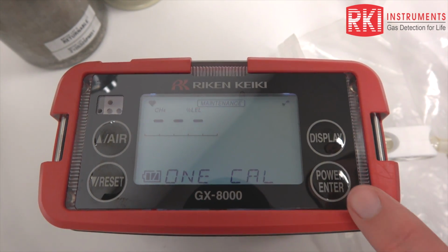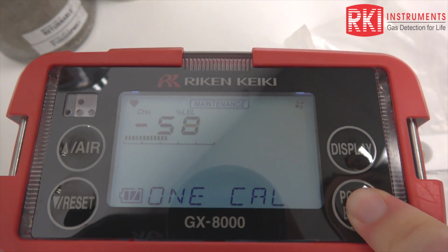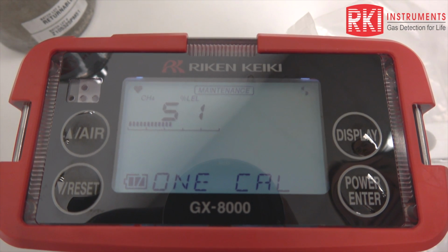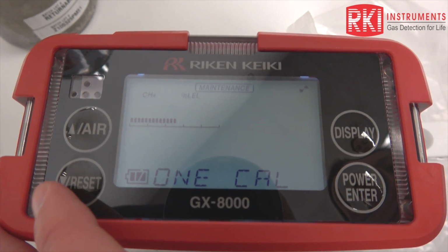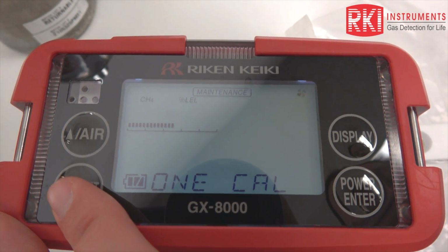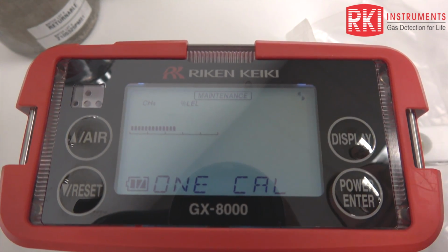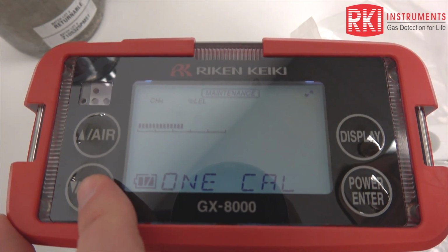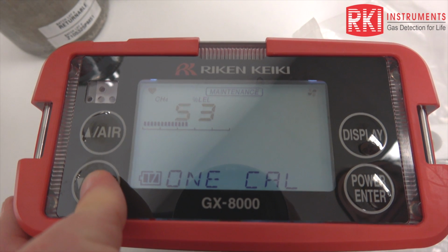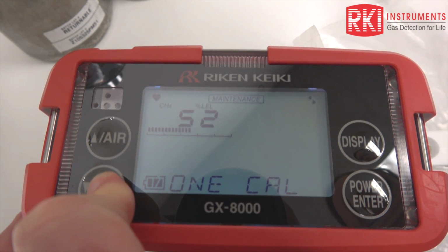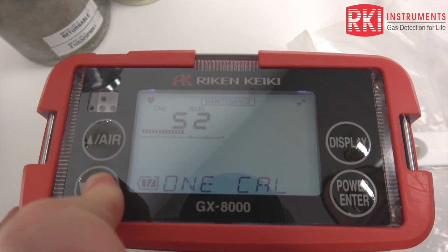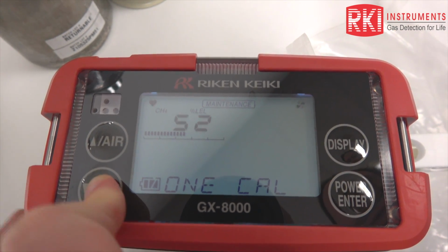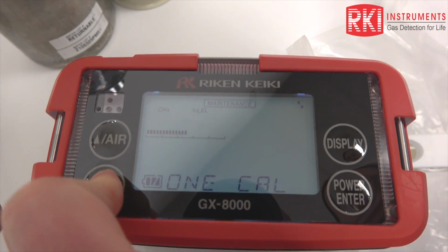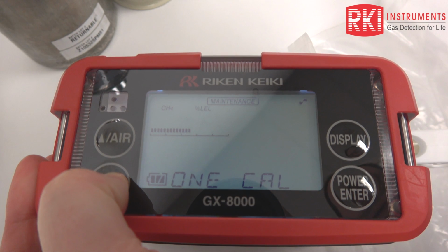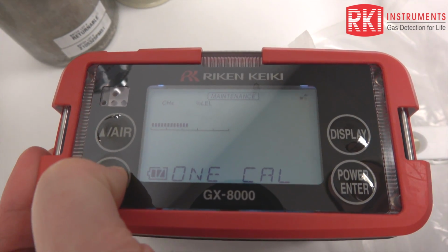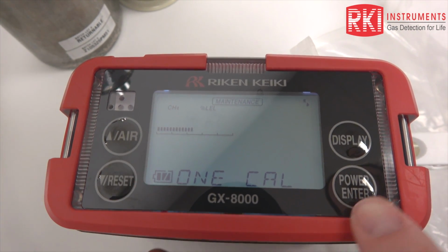We're going to start with the LEL combustible. I am using 50% LEL methane for my calibration. You need to use whatever gas is appropriate for your application. And it's also important that you calibrate the LEL combustible sensor before you calibrate the percent volume combustible sensor. Percent volume levels of gas will hurt your LEL sensor, and you need to let it have enough time to settle back down. So I need to get this reading to go down to 50% LEL because that's the concentration I have in my bag. There we go.